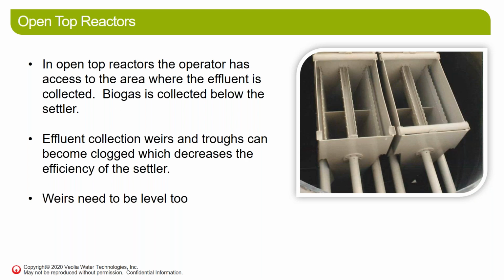So we have a couple different types of reactors, open top and closed top. Starting with open top, you can typically take off covers over the settlers where the effluent's coming out of the settlers to see them during operation and clean them. There's no major risk in taking off these covers because the biogas is collected under the settler and under the deck of the tank, and it's not coming out under these removable covers unless there's a major failure of the settler.